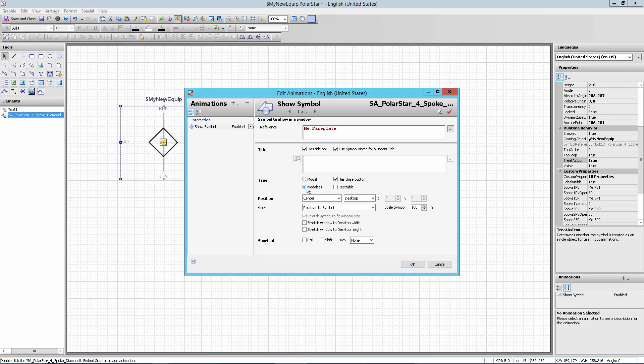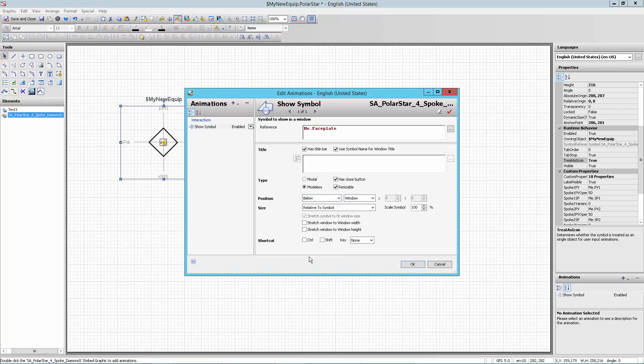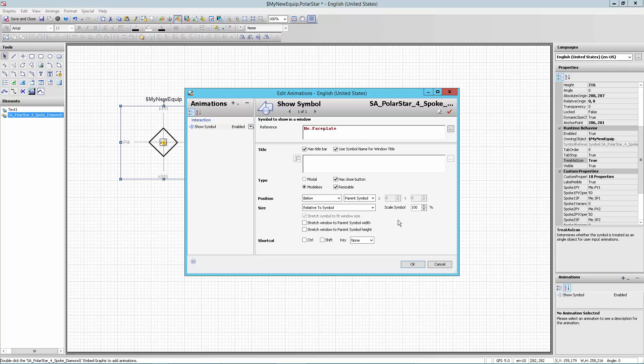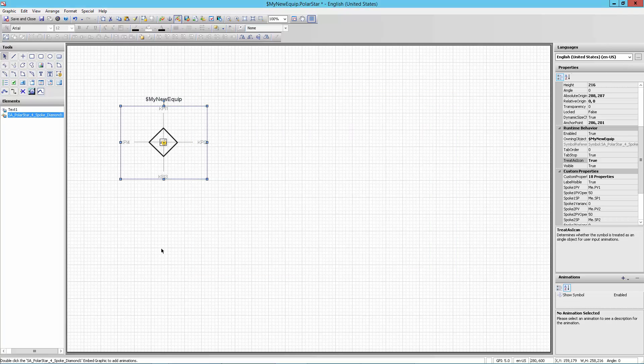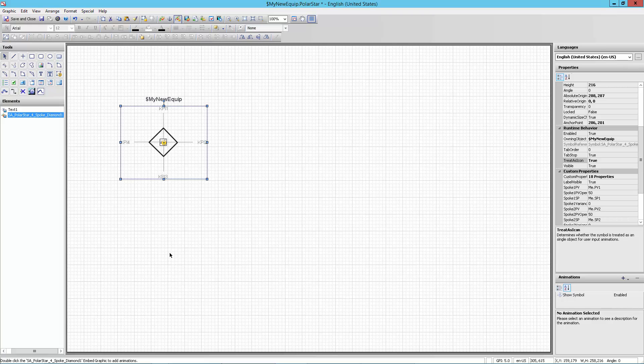I'm going to leave these things here defaulted. I'm going to go from modal to modeless. Modeless means that I can interact with this and the background at the same time. I'm going to make it resizable. And I'm going to say where do I want to put this thing? I'm going to put this thing below the parent symbol. So I'm going to have the pop-up come under the parent symbol or below the parent symbol. There are a lot of other options that we won't go into here, but that's just showing you the basics of how this was done. So I'm going to say OK to that. At this point, I've got everything I need on my symbol. I've got my name here, my polar star and my animation on the polar star to bring up my faceplate. So I'm going to go ahead and save and close this.